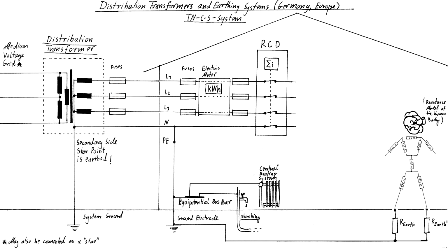After the conductors have entered the house, a set of fuses follow. If a short circuit would occur here, it would be these fuses rather than the earlier fuses that would blow. That is because there is a hierarchy of descending rated currents in these systems. In this way, a fault condition and a subsequent shutdown of a part of the grid stays as local and limited as possible. The same is true for all possible subsequent fuses and circuit breakers. So this is basically the first safety measure, preventing overheating and fire by recognizing overload and especially short circuit conditions.